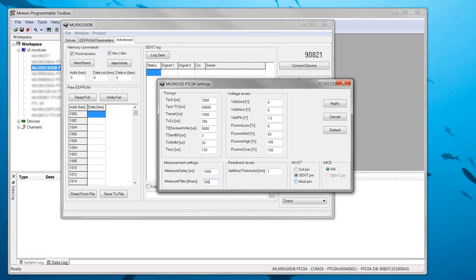The other settings relate to timings and voltage levels for communicating between PTC04 and pressure sensor. Most can remain their default value in all situations except for the setting T-sent-bit, which is the tick time used to decode sent output. By default, this is set to 3 microseconds, but when the sent output is configured with a different tick time, this setting has to be changed as well to decode the sent output with the PTC04. Click Apply before exiting the settings window.